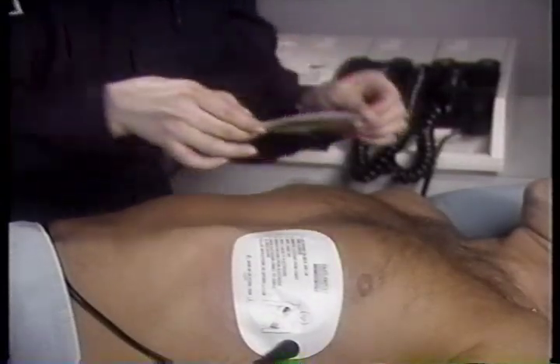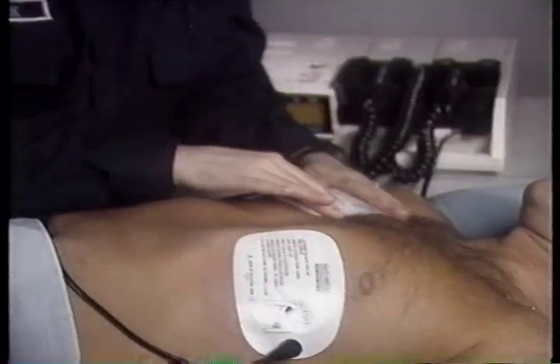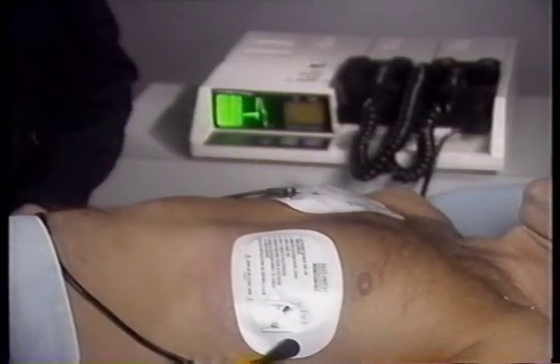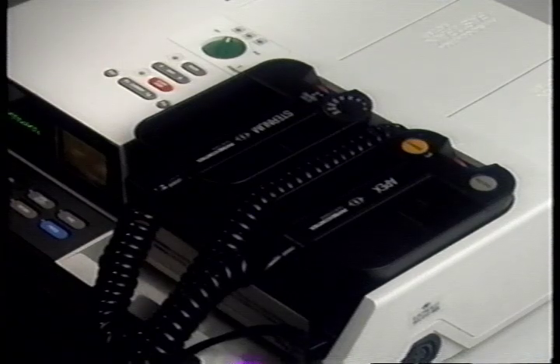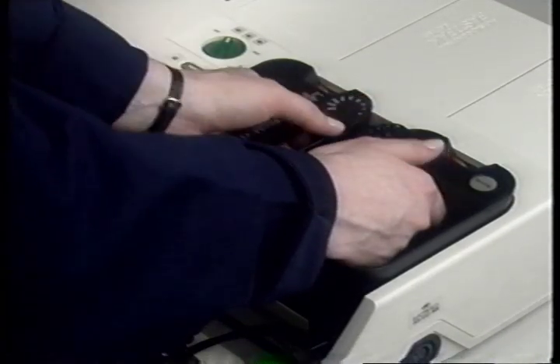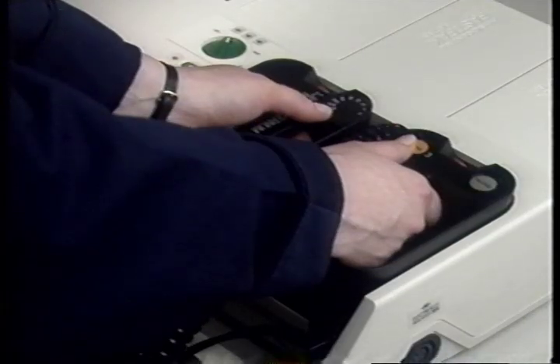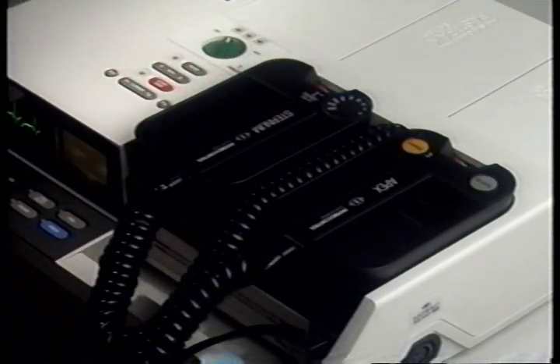The cable snaps are labeled for easy reference. Select the paddles mode by pushing Lead Select. This will provide a Lead 2 signal for monitoring. To defibrillate, leave the standard paddles in the fast patch adapter and follow the usual procedures for selecting the energy and charging the defibrillator. After warning others to stand clear of the patient and the bed, push both discharge buttons simultaneously to discharge the defibrillator. Remote or hands-off defibrillation eliminates the need for gel or paste, thus reducing the risk of arcing across the chest. Also, by placing defibrillation electrodes on high-risk patients, it can save valuable defibrillation setup time.